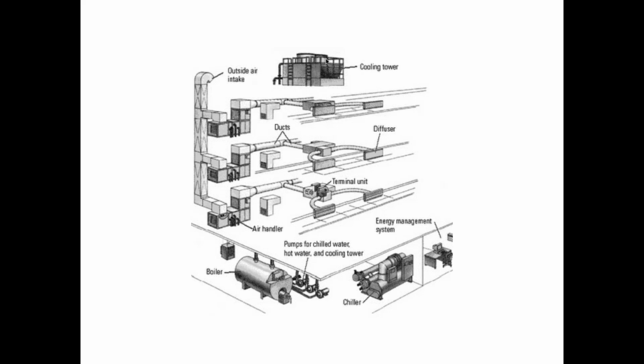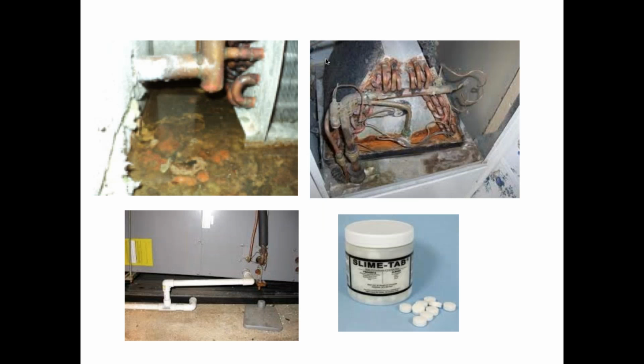In fact, they had a Ford plant where people in the buildings became ill because the cooling tower was infected with a high amount of Legionnaires bacteria, and the discharge from the cooling tower was getting sucked into the fresh air intake and infecting people in the building, right? So you want to make sure it's not close to the fresh air intake or openable windows, right? Anything that would wind up exposing people unnecessarily to it, right? So we got a lot of ways that these systems work.